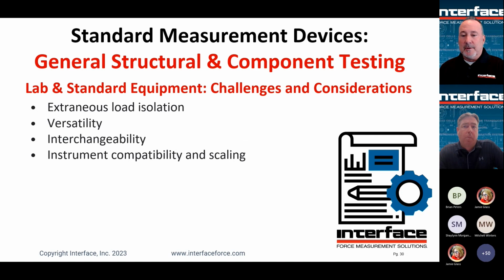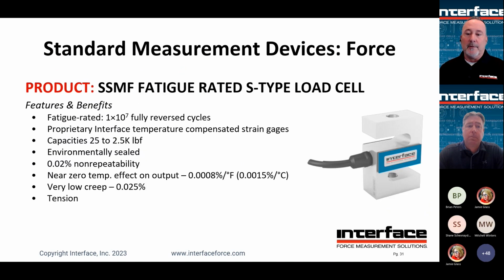The versatility and interchangeability. So that would be if you've got many different types of tests that you're doing, and you've got a variety of load cells or torque sensors on the shelf. Are those suitable to be used in many different types of tests, so that you're getting the most value there? And then also instrumentation compatibility. Do you have the proper instrumentation? Does it have the proper inputs to take the signals from these load cells or torque sensors, and does it provide you with the proper outputs for what you need to do, whether you're recording it and so on?